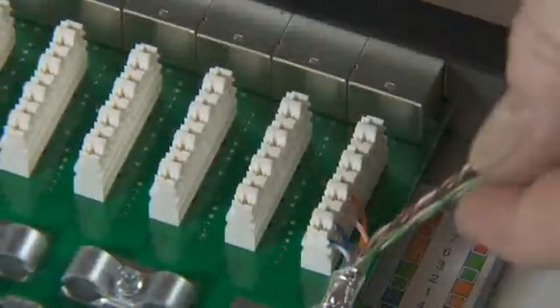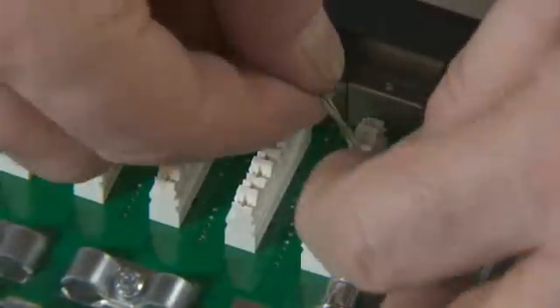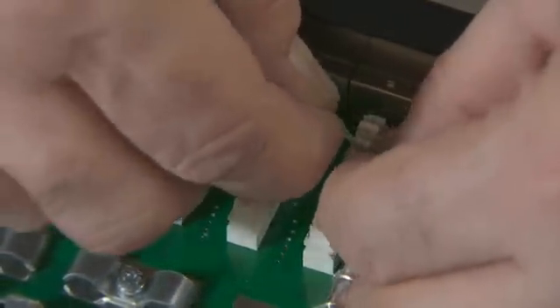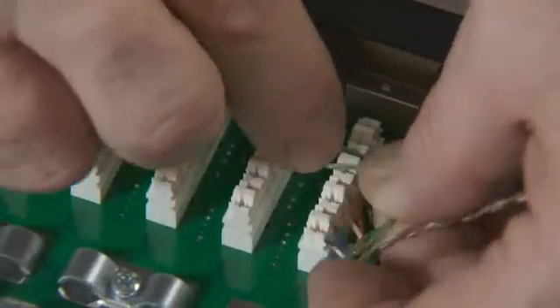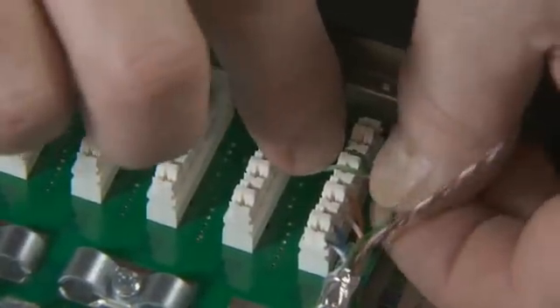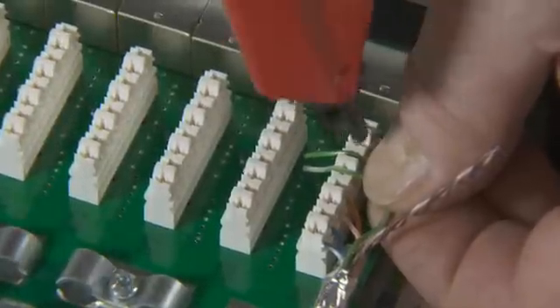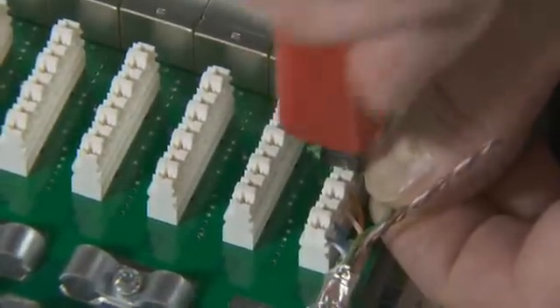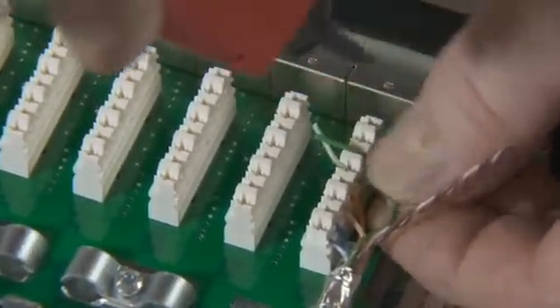Maintain the pair twists right up to the terminal block. It is preferable to add half a twist rather than remove half a twist when aligning the pairs with the termination blocks, and finally the white brown pair.